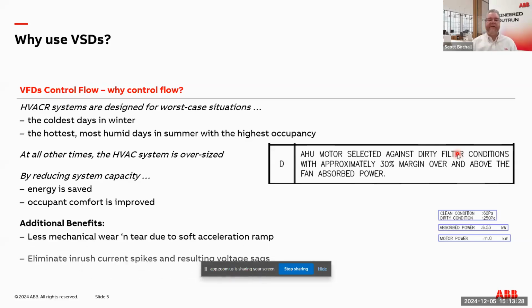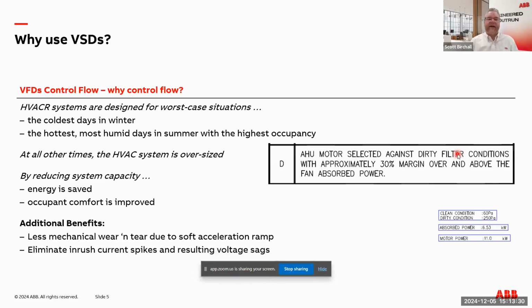Also, with drives, you get natural benefits. With air handlers starting direct across the line, when they pull in, all of a sudden you might hear a belt squeal. It puts a lot of wear and tear on that equipment. With drives, there's a natural soft-starting capability where we can ramp the motor up nice and slowly, so there's not as much mechanical wear and tear. It also eliminates the inrush spikes of current. I've seen it before where air handlers kick in and all of a sudden the lights dim for half a second because of that voltage sag. Those are all things that don't happen when you have a drive. So other than the basic comfort, variable speed capability, and energy savings, there are also those fringe benefits of having variable speed drives on applications.